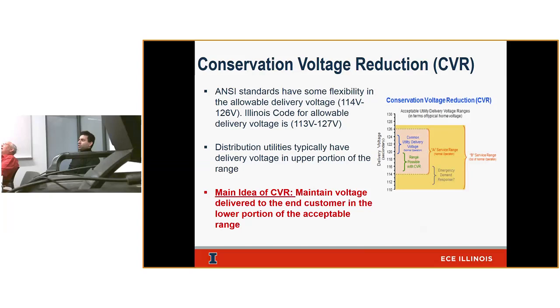To take a very conservative approach, we peg the voltage regulators and LTCs as high as possible at the substation feeder head. If a voltage regulator is set at 128, that's a violation. Sometimes when the voltage regulator is acting a little weird, you'll end up seeing violations for customers right outside the substation — they will see the largest voltage magnitude on the circuit.